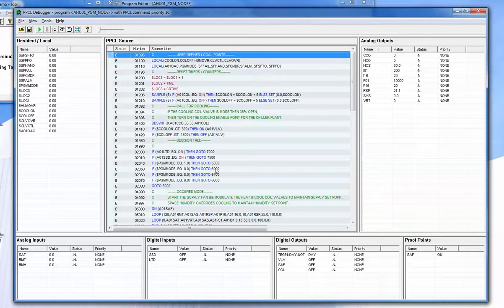There's only a PPCL evaluator and no restrictions from the firmware. Normally, firmware adds restrictions to the PPCL, but not here. For example, if PPCL commands a point, but that point was commanded somewhere else at a higher priority, normally the firmware rejects the PPCL command. In the debugger case, the evaluator actually allows that to happen.